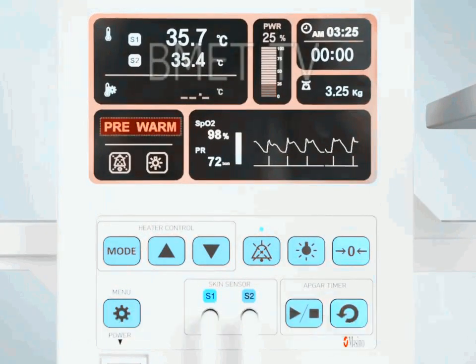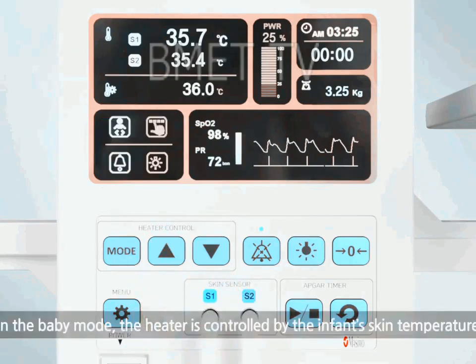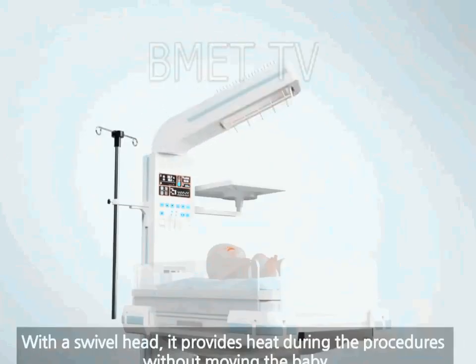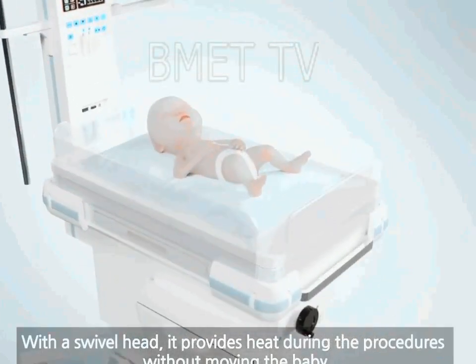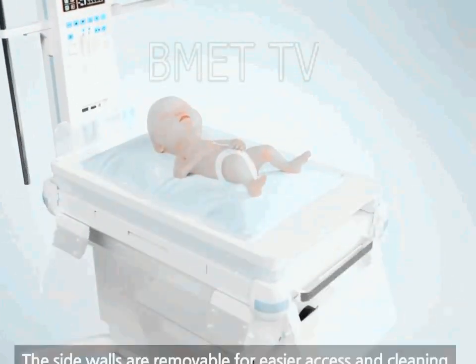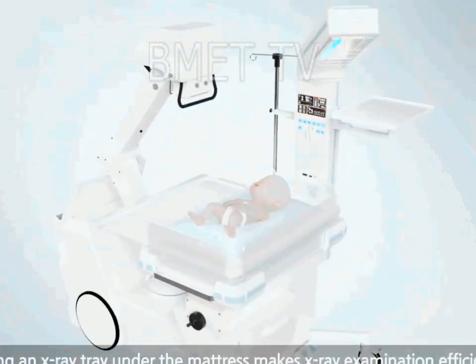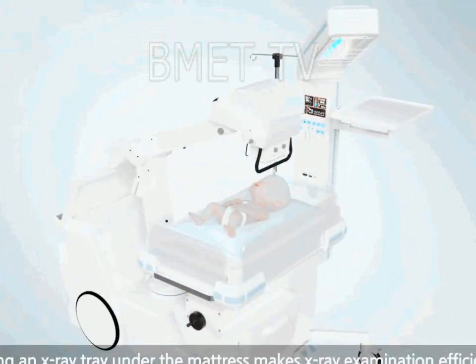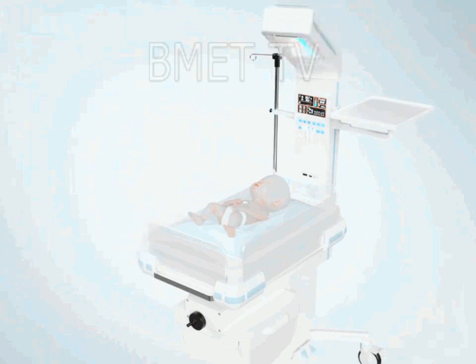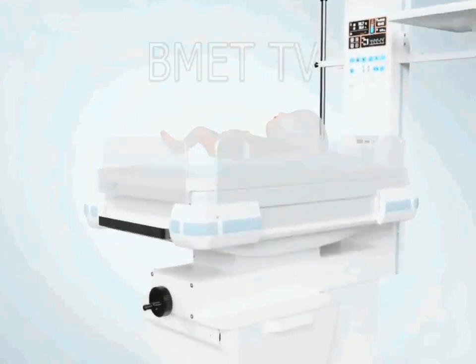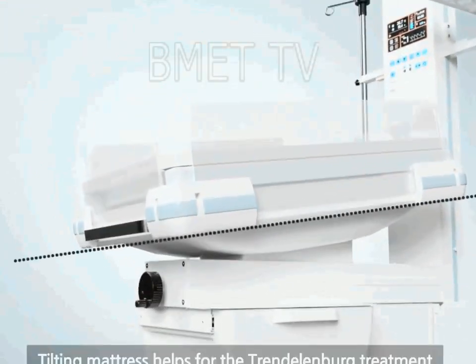they can achieve self-thermoregulation. Monitoring and resuscitation can easily be performed from the open access of a radiant warmer, along with any necessary procedures. Radiant warmers are also used for critically ill patients that require constant nursing intervention. Radiant warmers are usually overhead heating units, consisting of a heat source, skin temperature sensor, servo control unit, and both visual and audible alarms. The heating element generates radiant energy in the far IR wavelength region, but is limited to prevent thermal damage to the infant.